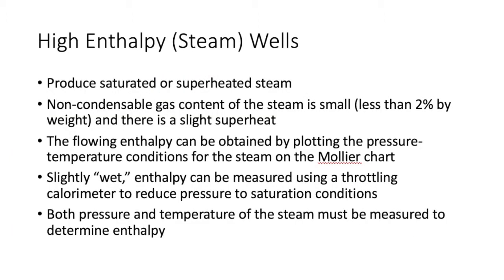High-enthalpy steam wells produce saturated or superheated steam. The flow rate is measured by an orifice or pitot tube and temperature measurement techniques. If the non-condensable gas content is small — less than two percent — the flowing enthalpy can be plotted using pressure-temperature conditions on the Mollier chart. If the steam is slightly wet, enthalpy is measured using a throttling calorimeter to reduce pressure to saturation conditions. Pressure and temperature both need to be measured simultaneously to determine enthalpy.